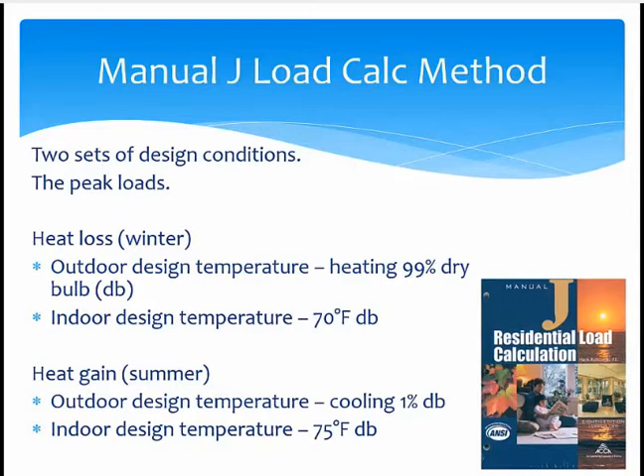For the winter, we have two design temperatures used in the load calculation. The outdoor design temperature will be the heating 99% dry bulb temperature — that is, 99% of the year, over 8,600 hours, it will be warmer than this temperature. So that's pretty cold. Meanwhile, the indoor design temperature is going to be 70 degrees Fahrenheit dry bulb.